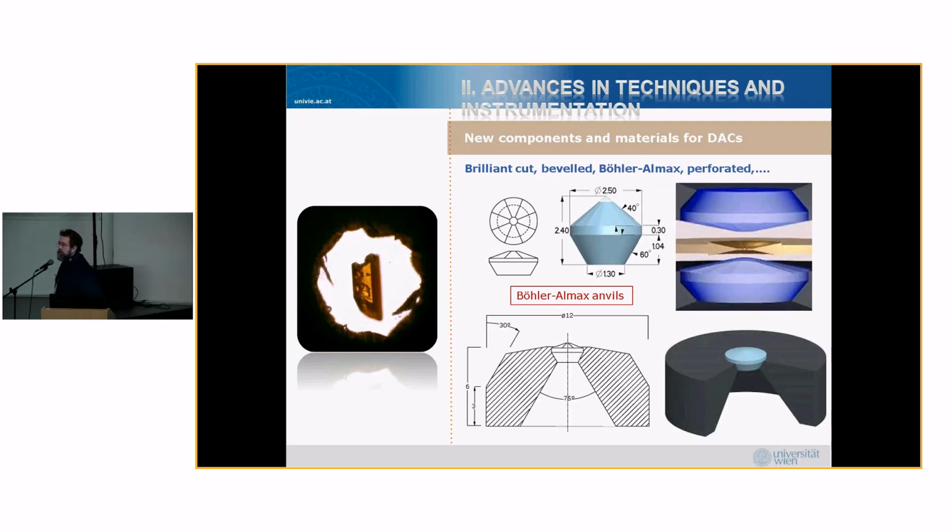The other invention that has been made, and was a very good one, also about 15 years ago, has been done by Reini Böhler, who is now in the US, and was previously in Mainz. He designed, together with a Belgian company which produces these diamond anvils, a new shape to give a support for the diamond through the seat underneath. And this is very helpful. It's like a simple construction, like a bridge. If you think of a bridge, it's also not collapsing because you have this support on different parts of your architecture.